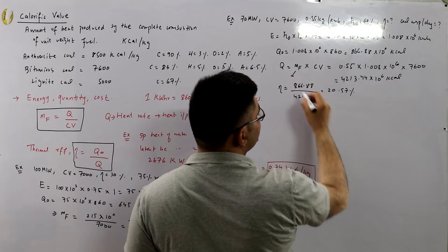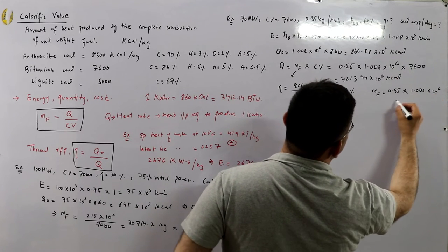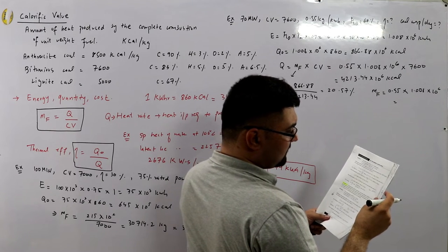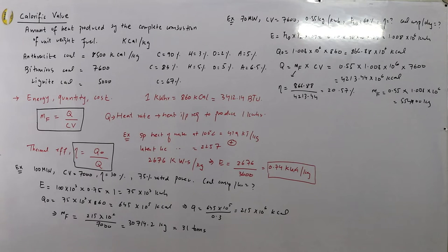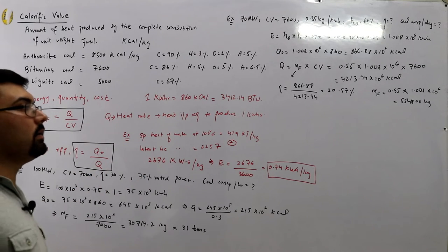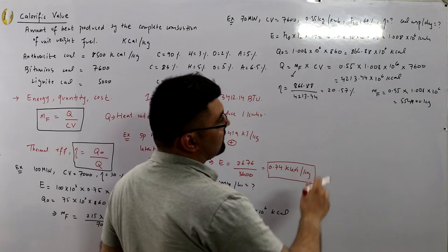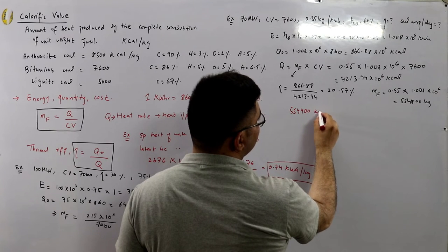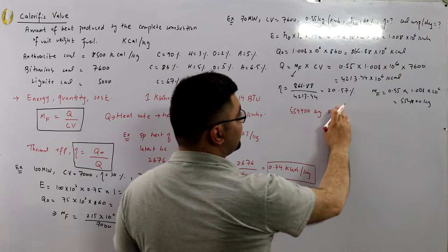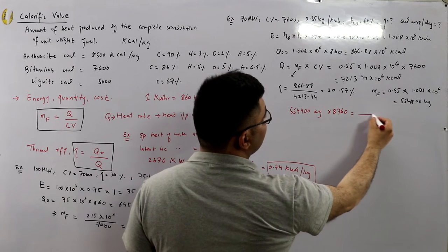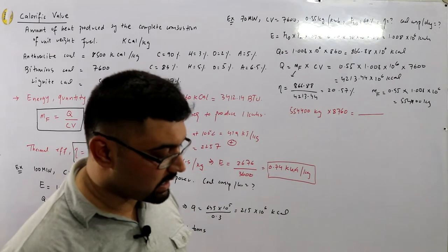Coal consumption per day: mass of fuel = 0.55 × 1.008×10⁶ = 554,400 kg. Multiply by 24 for daily consumption, or by 8760 for annual consumption. Multiplying by cost gives the total money spent.